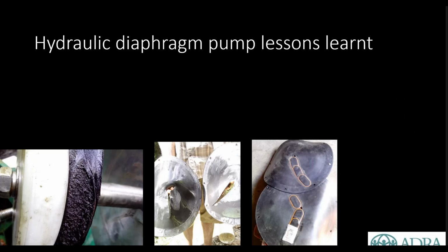So you can see on your screen in a minute, you'll see popping up a few issues that have been experienced with the pump in Tanna. The image on the left actually shows some pitting, which is from grits and things like that getting through the system. And also maybe the adjustment was probably not quite set up right at the first installation, and it's allowed that cup to rub on the piston inside the pump.